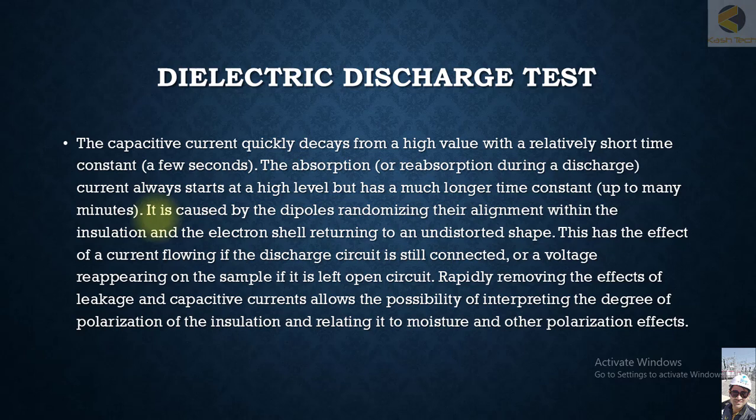This has the effect of a current flowing if the discharge circuit is still connected, or voltage reappears on the sample if left open circuit. Rapidly removing the effects of leakage and capacitive current allows the possibility of interpreting the degree of polarization of the insulation and relating it to moisture and polarizing effects. This is fundamentally how the Dielectric Discharge Test works.